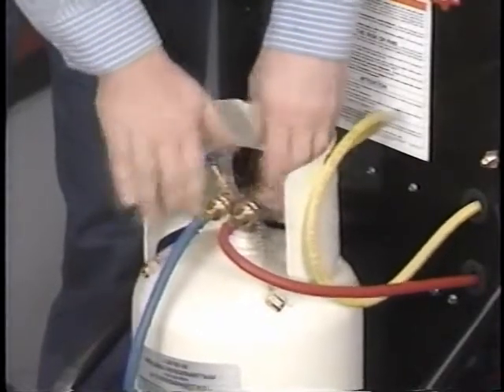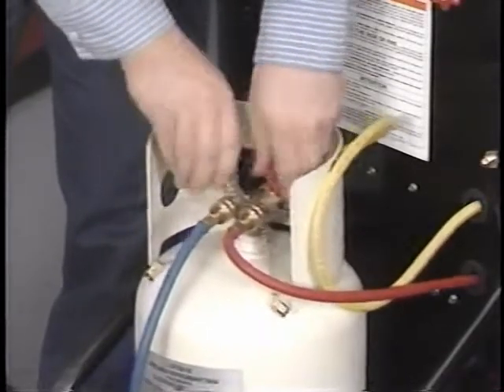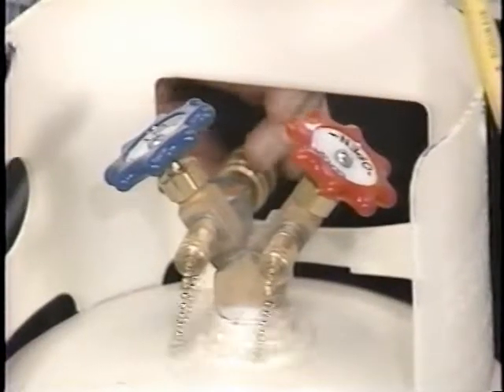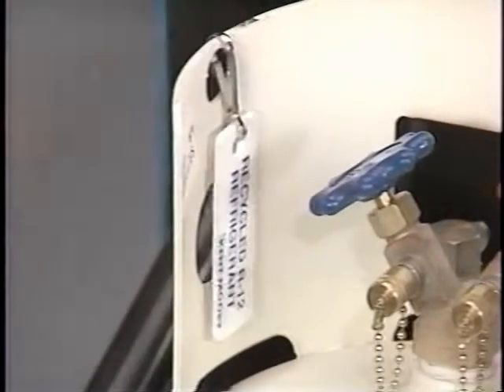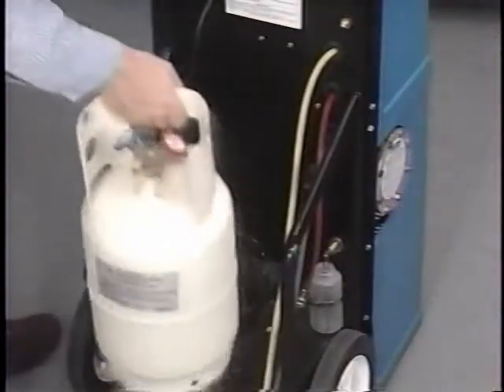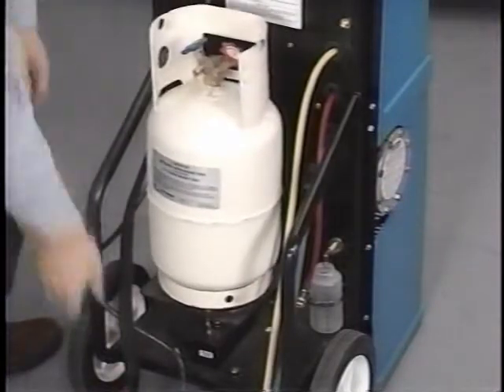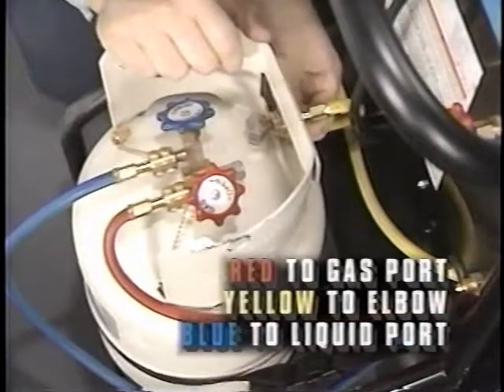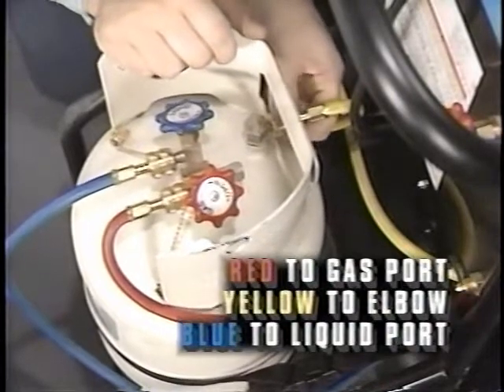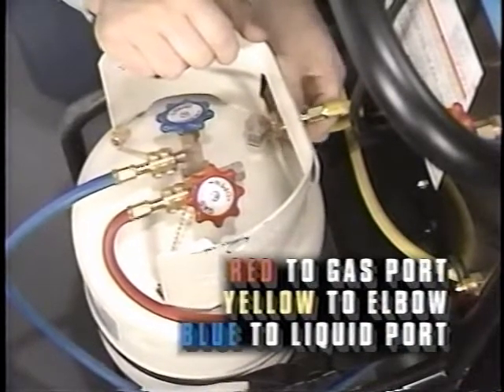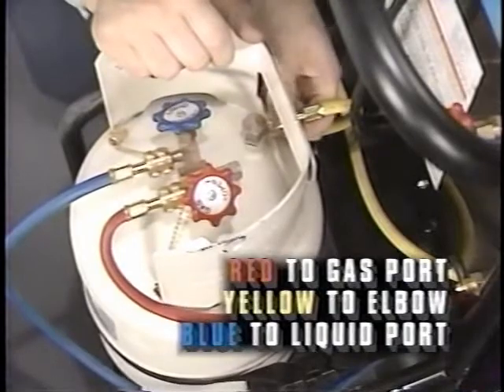To remove a full tank, close both valves. Then, disconnect the 3 hoses from the tank. Then remove the strap and set the tank aside. Place an empty tank on the platform and attach the strap. If the empty tank has already been used, it's not necessary to pull a vacuum on the ACR3 system. Reconnect the hoses. The system is now ready to recover more refrigerant, and the recycled tank is ready to charge AC systems.